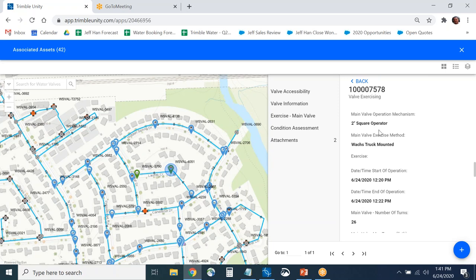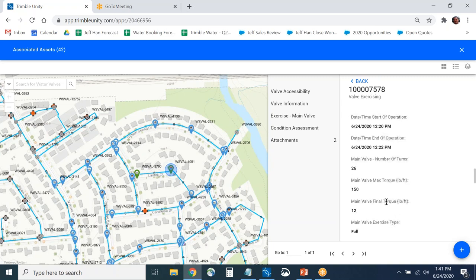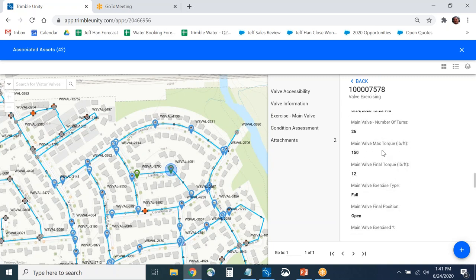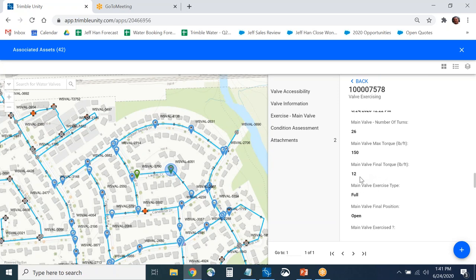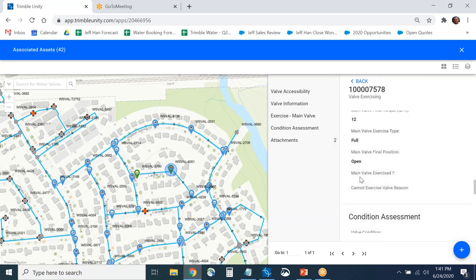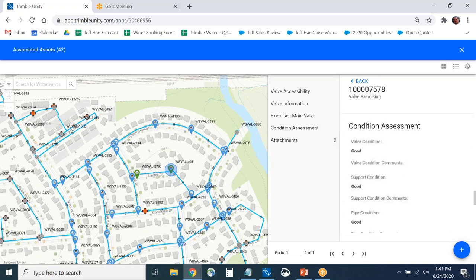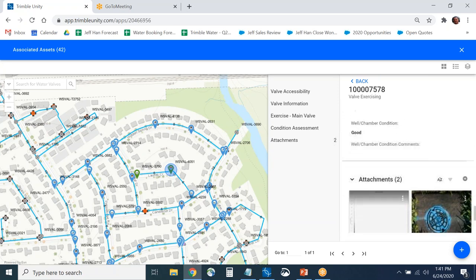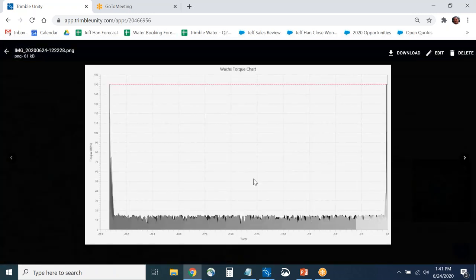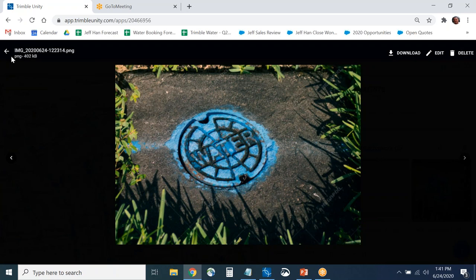The actual valve exercising page shows the exercise was done with the Wachs truck mounted, started at 6/24 at 12:20, ended at 12:22. You can see the number of turns, maximum torque, final torque, whether the valve was operating completely, and condition assessment information filled out in the field. The actual torque chart related to that inspection is viewable, along with a picture that was taken.